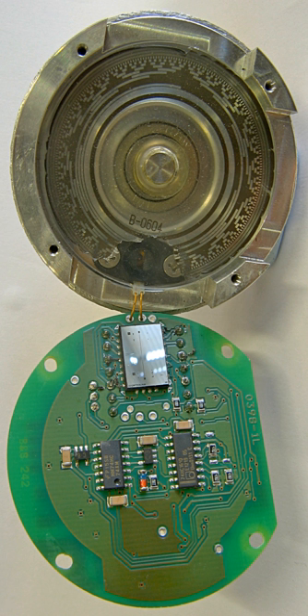Magnetic absolute encoders. The magnetic encoder uses a series of magnetic poles, two or more, to represent the encoder position to a magnetic sensor, typically magnetoresistive or Hall effect. The magnetic sensor reads the magnetic pole positions. This code can be read by a controlling device, such as a microprocessor or microcontroller, to determine the angle of the shaft, similar to an optical encoder.